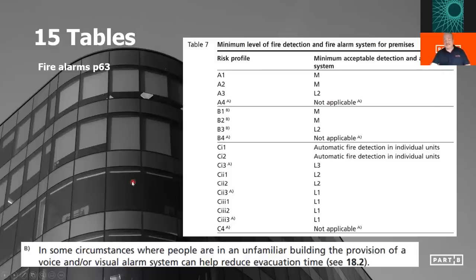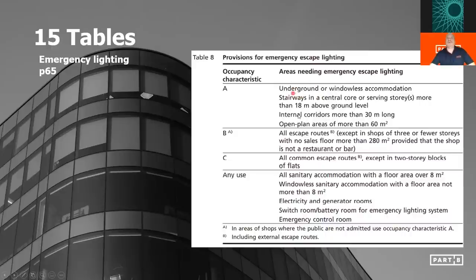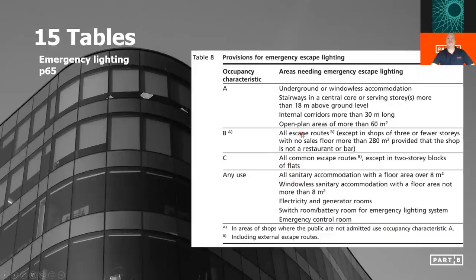Fire alarms are covered in BS9999 to some extent, though not to the level of detail of BS5839 — it's just about the provision of what type of system you'd expect to see. Moving on to Table 8, which talks about the emergency lighting system: it's not so interested in the risk profile, but it's very interested in the occupancy characteristic of a building. Occupancy characteristic A tells you the areas that need emergency escape lighting. Occupancy characteristic B tells you additional areas. And there's a 'any use' row at the very bottom that is easy to forget, which applies across all occupancy types.